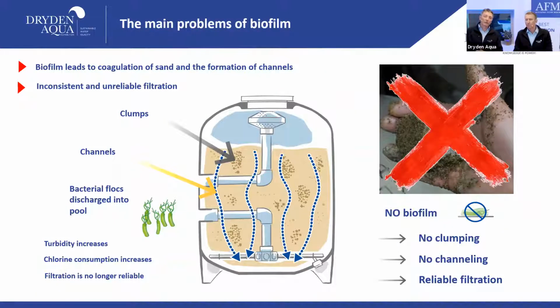And maybe another point to this. We have seen 2 pictures. One that Philip showed, where you have seen on this electron microscope this grain of sand colonized with bacteria. This is how sand looks after 2-3 days. It will take a lot longer, 6 to 12 months, depending on the temperature and depending on the load, until it looks like here on this picture, with the red cross. You have such a heavy biofilm that the sand grains are really glued together. And this is where you get the channeling. And Philip will explain why it takes 6 to 12 months to get to these conditions.